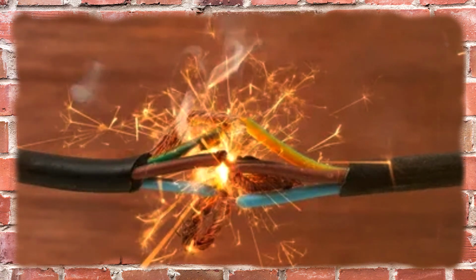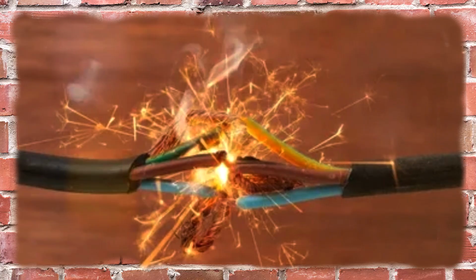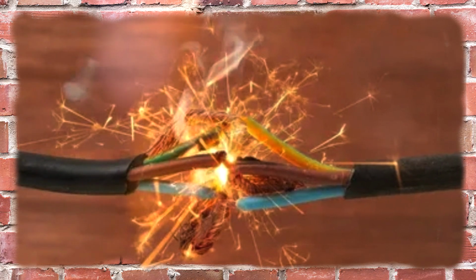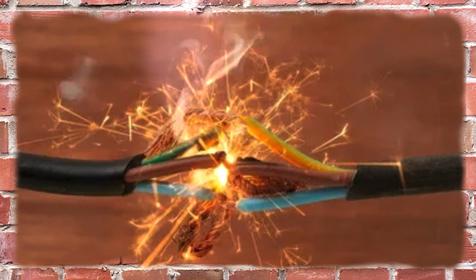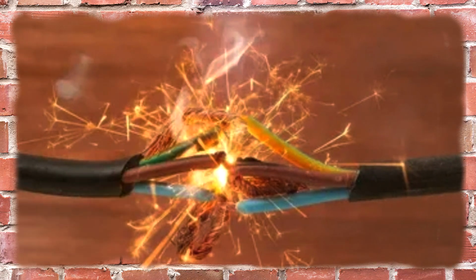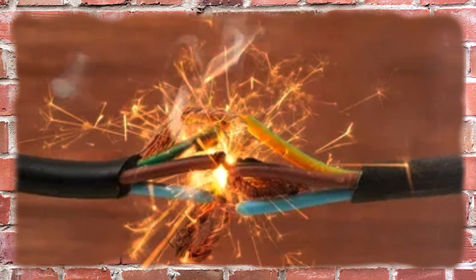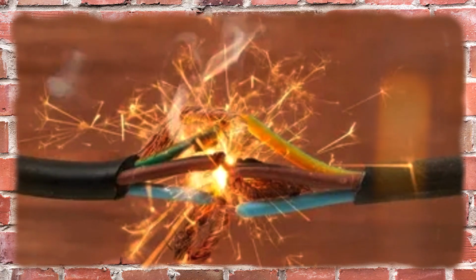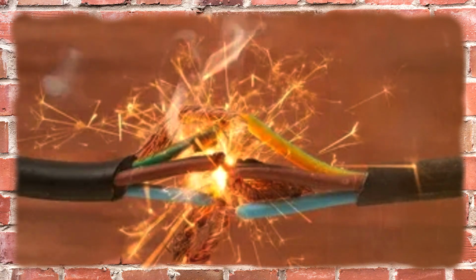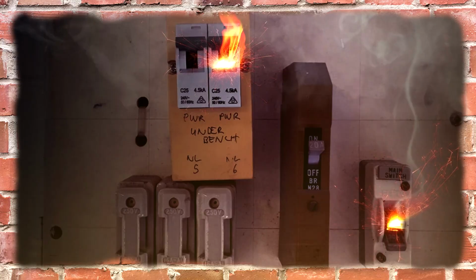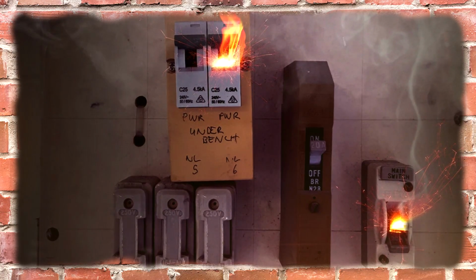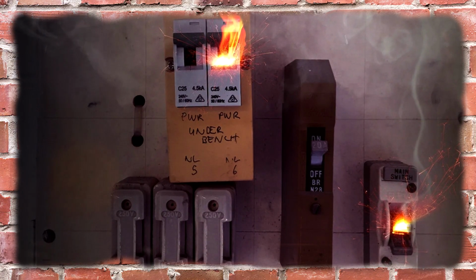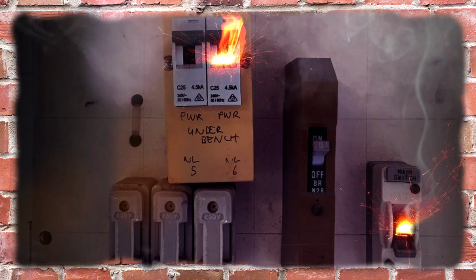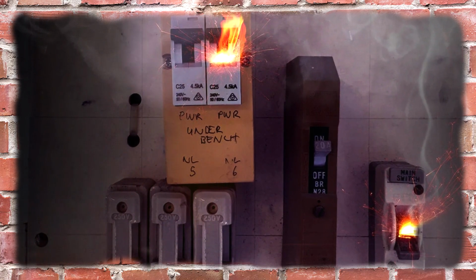Yet Europe imposes tougher fire safety cable rules. CPR, Construction Products Regulation, fire reaction class is mandatory, with class B2ca or higher required for dwellings. Cables must resist flame spread and emit minimal smoke or toxins, while in the US, such rules mainly apply to public buildings. Private homes may use standard PVC insulated cable, which emits toxic hydrogen chloride when burning.